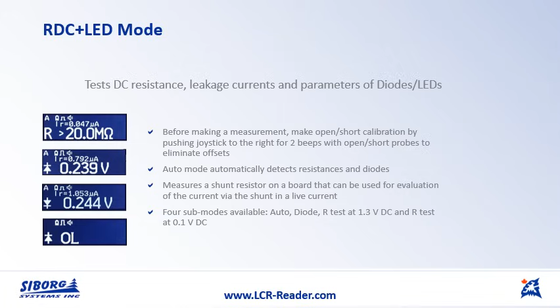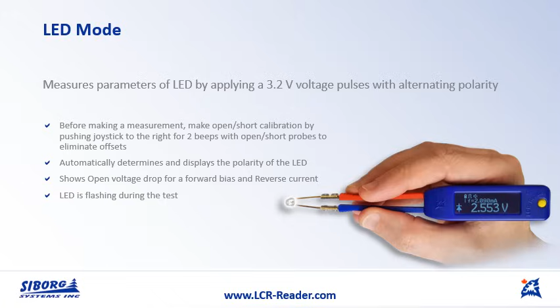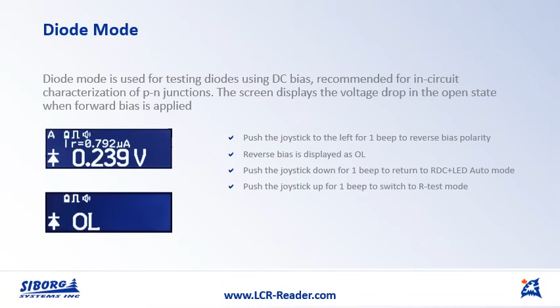LED mode applies 3.2 volt voltage pulses with alternating polarity, so that it determines the forward voltage drop and reverse current. The diode mode is used to test diodes using DC bias, recommended for in-circuit characterization of PN junctions. The screen displays the voltage drop in open state and when the forward bias is applied.